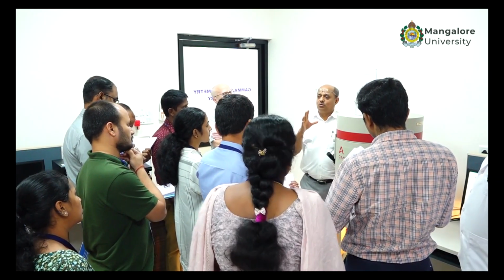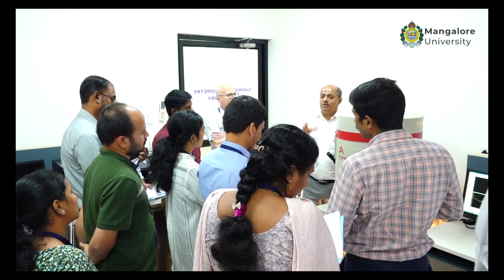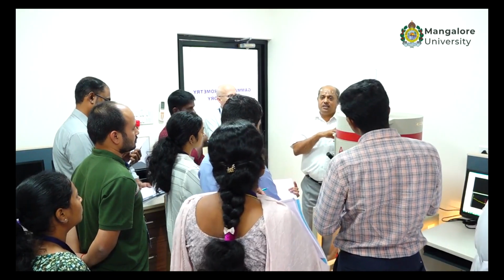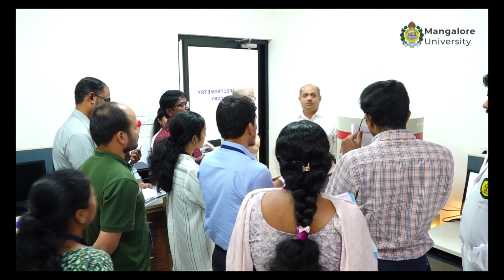Previously it used to be relative efficiency, in comparison to sodium iodide. Sodium iodide was considered to be the benchmark detector. Then later this came, so you compare the efficiency of HPGe relative to sodium iodide. Subsequently, they started reporting it as nominal efficiency.